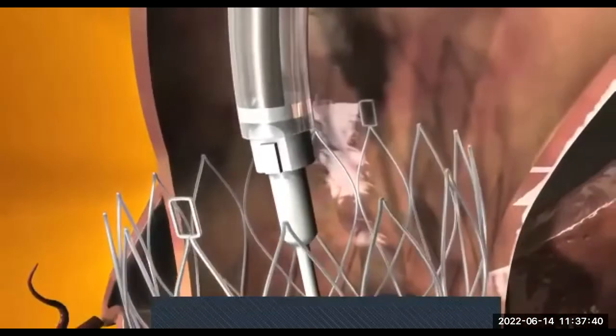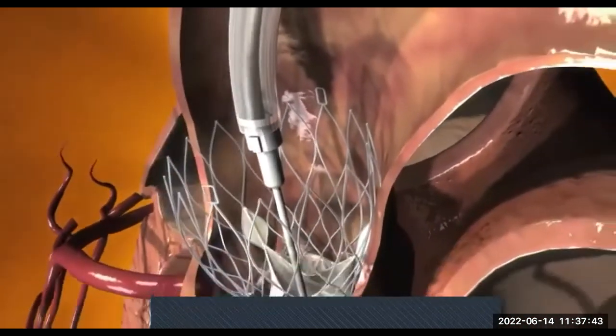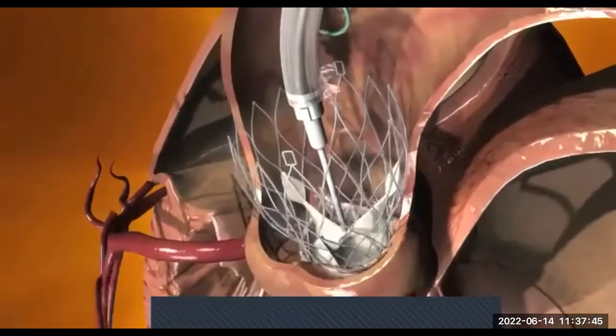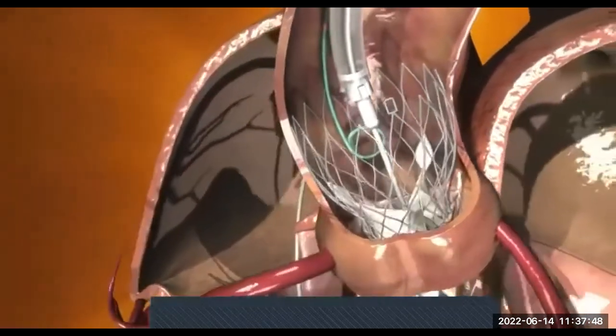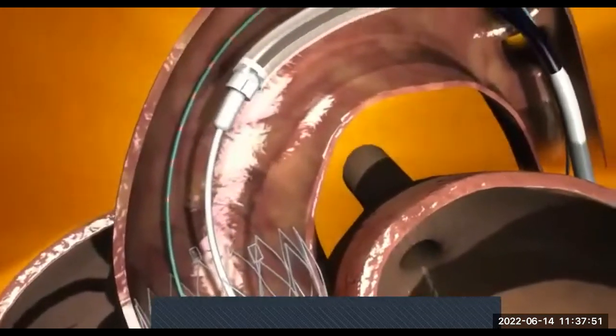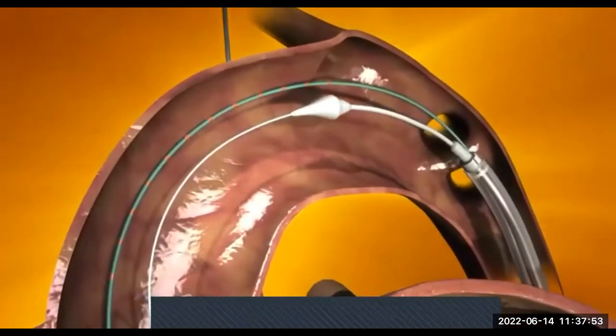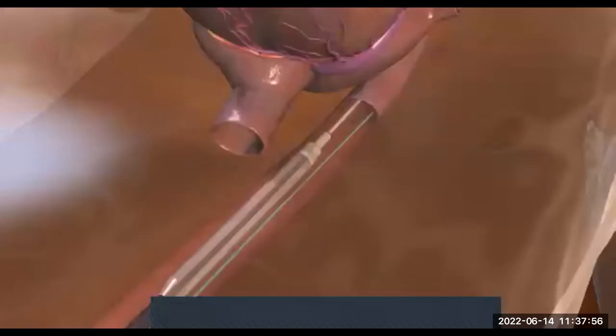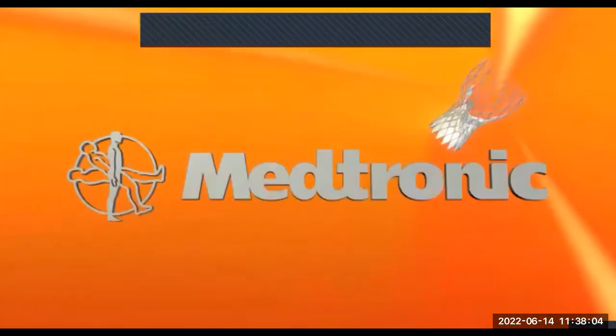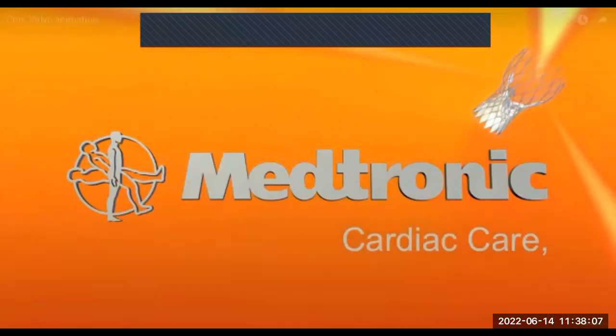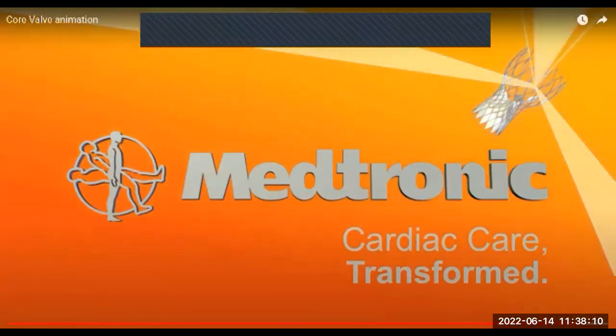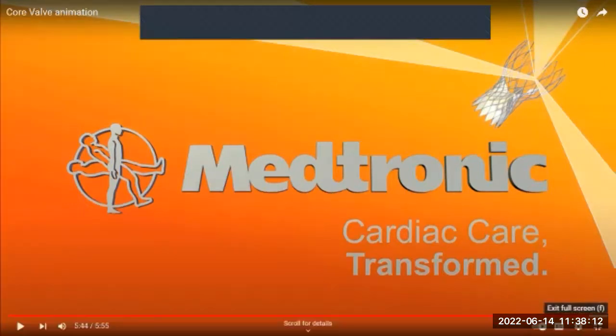Note, it is critical that you confirm that both loops have disengaged. Failure to do so may cause inadvertent movement of the valve from its intended position. Withdraw the catheter into the descending aorta. Close capsule and recover the entire system. And that is the two valves that we use at the New Brunswick Heart Center.